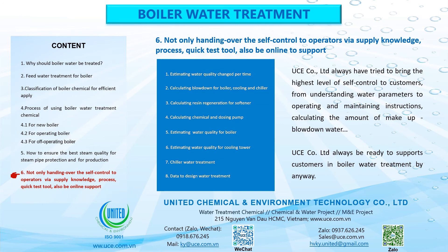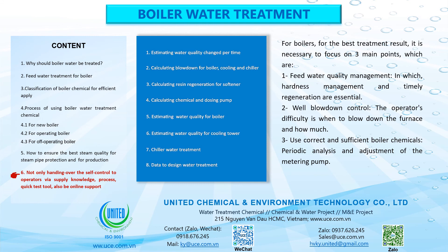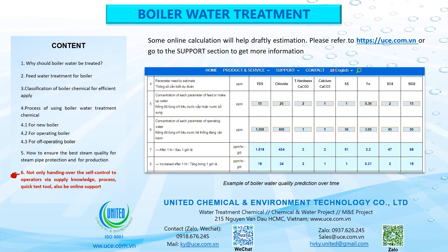6. UCE Co. Limited always strives to bring the highest level of self-control to customers — not only handing over self-control to operators via knowledge, process, and quick test tools, but also being online to provide support — from understanding water parameters to operating and maintaining instructions, calculating the amount of makeup water and blowdown. For the best boiler treatment result, it is necessary to focus on three main points: 1. Feed water quality management, in which hardness management and timely regeneration are essential. 2. Well blowdown control — the operator's difficulty is knowing when and how much to blowdown. 3. Use correct and sufficient boiler chemicals, with periodic analysis and adjustment of the metering pump. Some online calculation tools will help with rough estimation. Please refer to https://uce.com.vn or go to the support section to get more information.